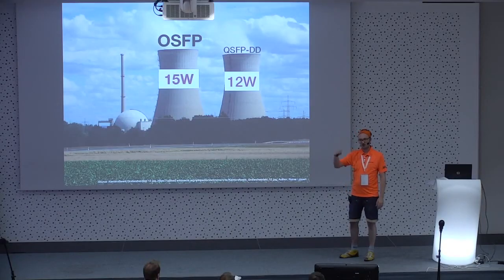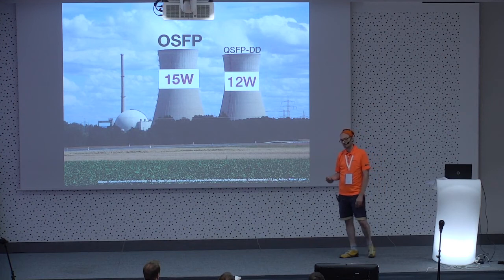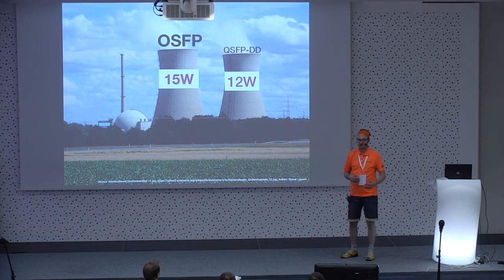So I'm pretty sure there will be 1U switches out there reaching almost 1 kilowatt of heat dissipation in 1U. That's quite a lot. Thinking about your rack having 40 or 42 units in there, that's a lot of heat dissipation. So the 100 millimeters from the front to the front door are, I think, pretty important. It's going to be a big heater.